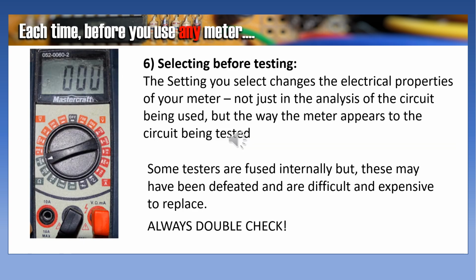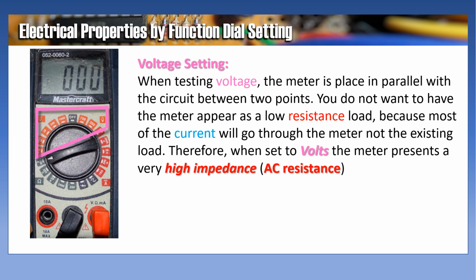Selecting before testing. The setting you select changes the electrical properties of your meter, not just in the analysis of the circuit being used, but the way the meter appears to the circuit being tested. Some testers are fused internally, but these may have been defeated and are difficult and expensive to replace. Always double check. Alright, so let's take a look at the electrical properties by function dial setting.